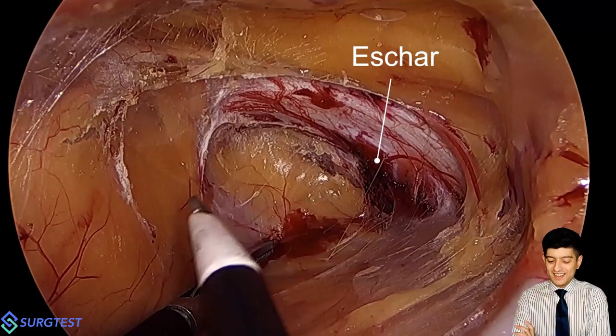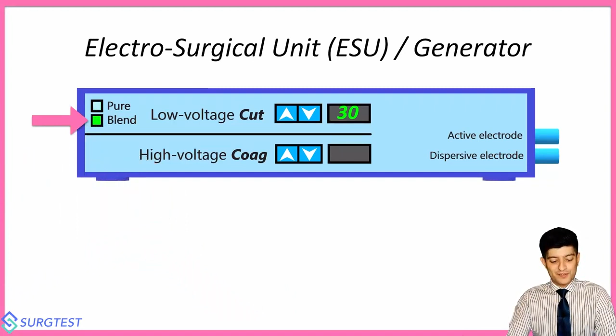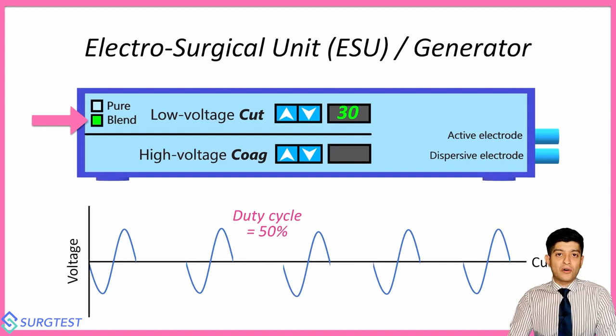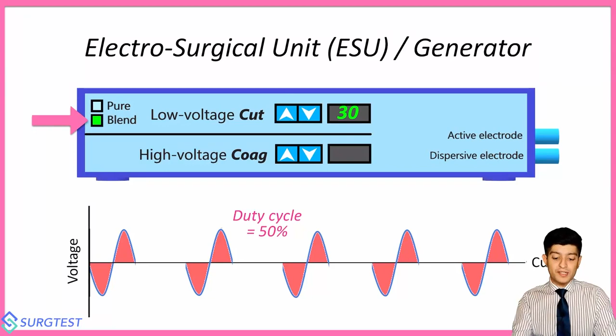All right. So let's go back to the ESU. There's also a blend mode. What exactly is this? Now, there is no color coding for the blend current. I'm just going to use pink right now for the heck of it. All right. I'm setting the ESU again to 30 watts and using a blend mode. And this is the sort of current that you're seeing right now. So it's definitely not a continuous current, but the duty cycle has to be higher than what we see in a coagulating current, right? On average, the blend mode is going to have a duty cycle of 50%, which means the current stays on for 50% of the time and off for 50% of the time. And this is the area under the curve, which conforms to 30 watts in this particular case.